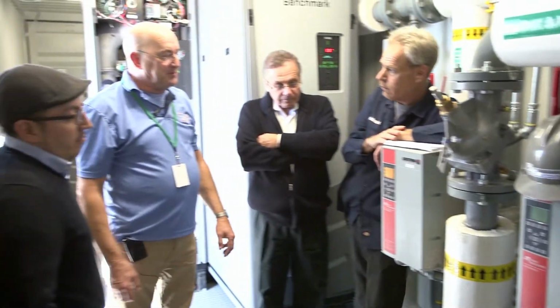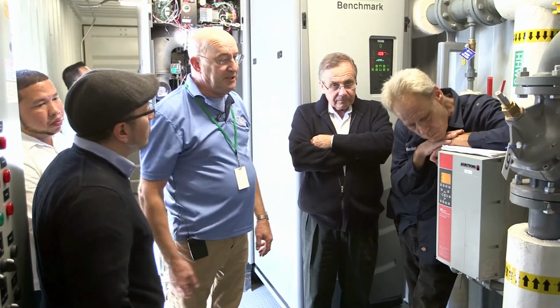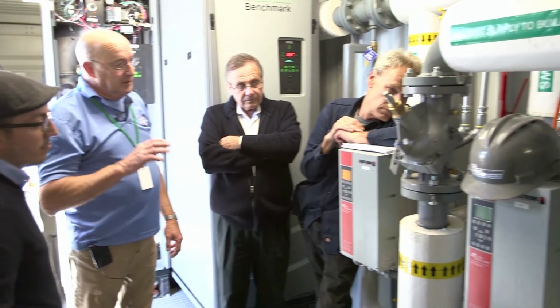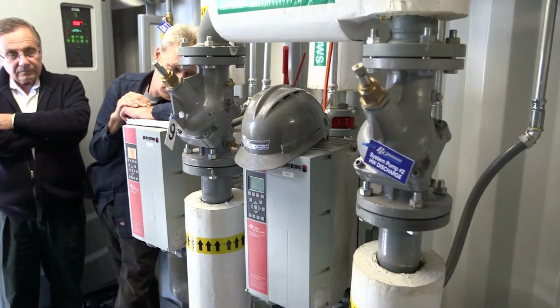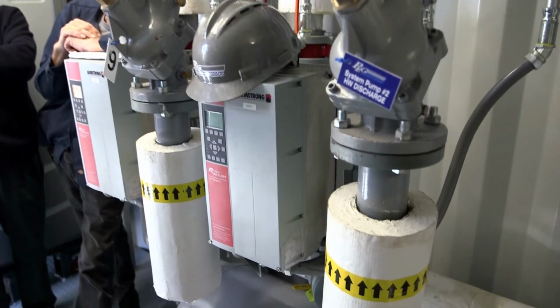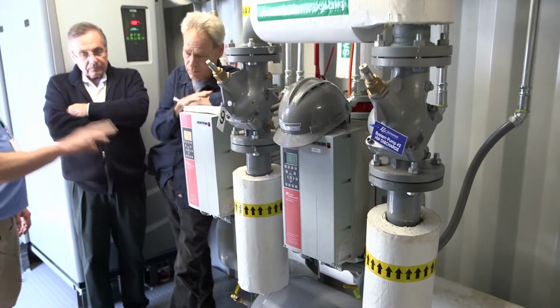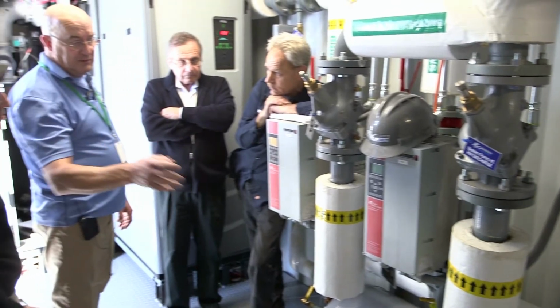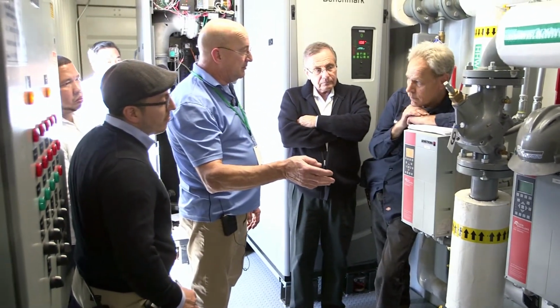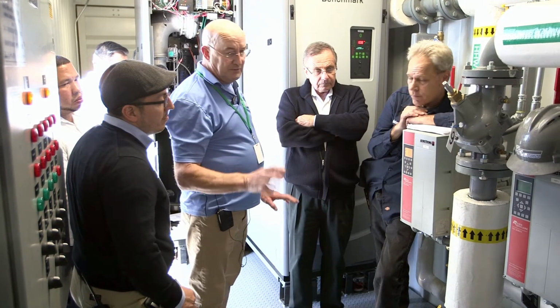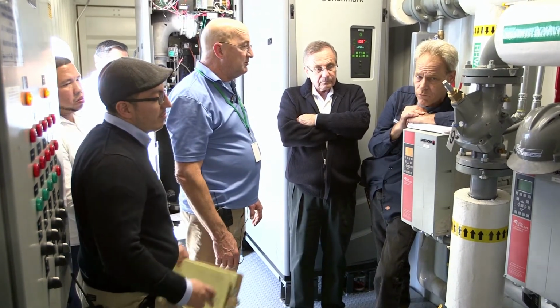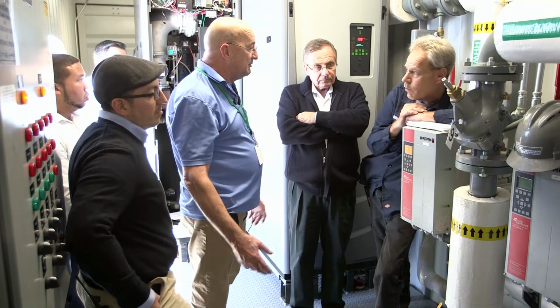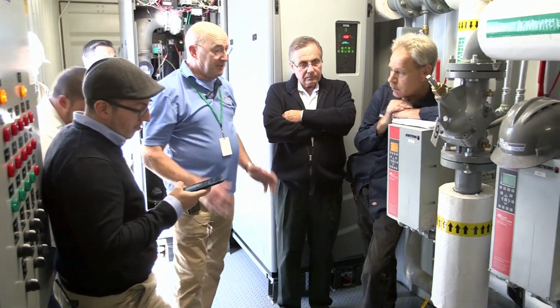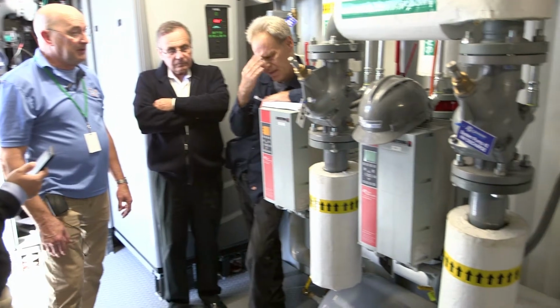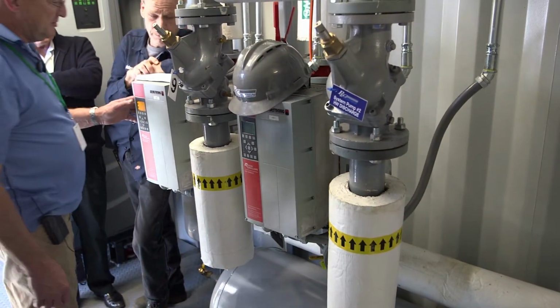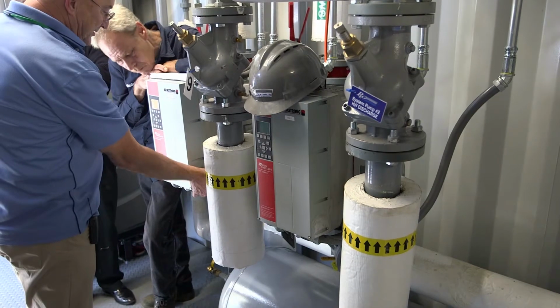Two large VFD pumps. These supply the heat to the building. Redundancy, everything's redundancy as you see in the trailer. There's backup for everything. Same thing, one will run at a time. They'll rotate every 96 hours and switch on and off. No need for you to run two at the same time. It's not going to make the system any better or any worse. It's just to run efficiently. Just a backup. Again, there's valves on these.